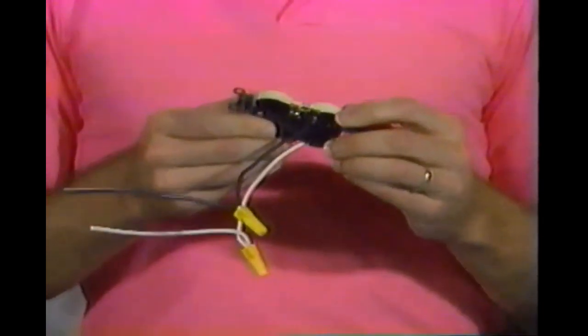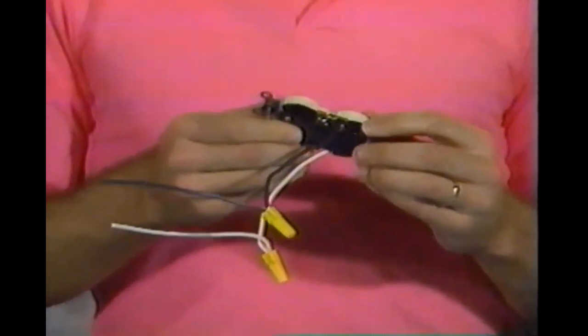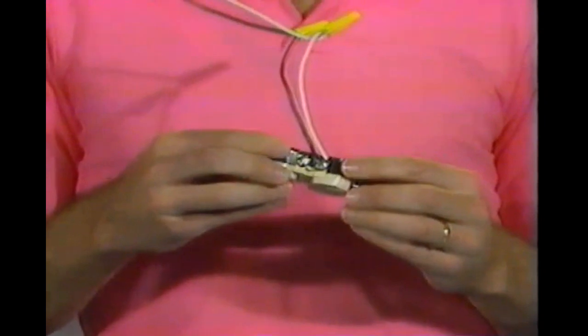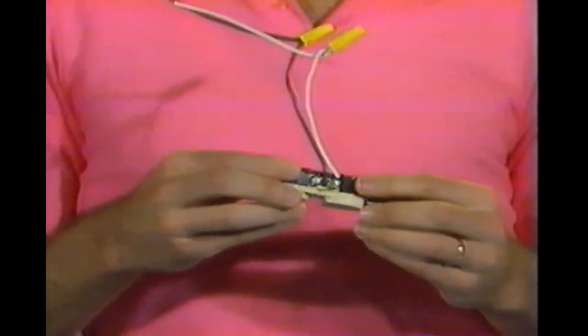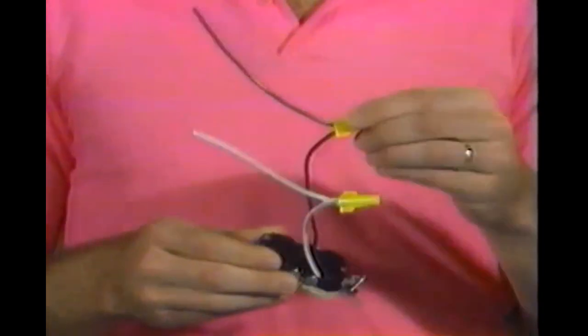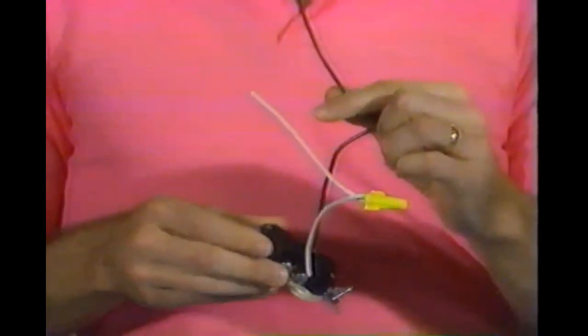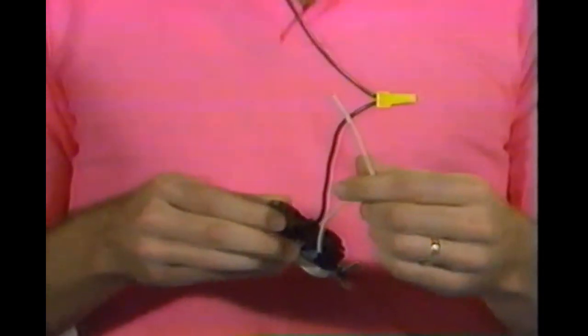As a safety measure, we suggest using a pigtail. A black copper wire is attached to the dark terminal, and a white copper wire is attached to the white or silver terminal. They are then attached with wire nuts to the hot aluminum wire and the neutral white wire, respectively. This bypasses the point where most aluminum-related fires originate.